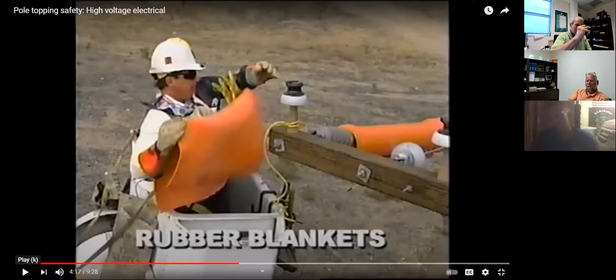5,000, Robbie? Even at 2,400 volts, which is the lowest primary voltage, that's 4,160 phase to phase. So 5,000 is a small margin, right there on the rubber glove side.